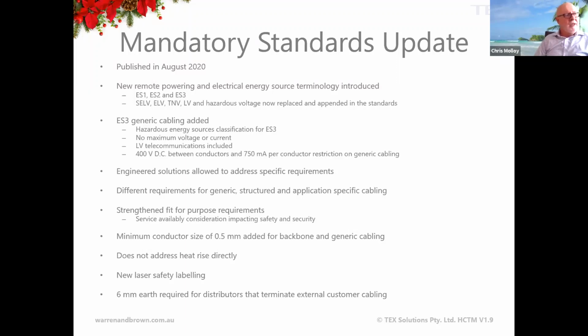There's a new naming convention now for remote powering and electrical source equipment, energy source equipment definitions. They come from a standard called AS/NZS 62368.1, and they have been applied. So we now have ES1, ES2, and ES3, replacing what we used to call SELV, ELV, TNV, and low voltage telecommunications and hazardous cabling. Those have been appended to the standards, and there is a changeover period for the next 18 months of swinging that terminology across. So if you haven't seen these standards, I can't implore you enough to get hold of them and get your head around how ES1, ES2, and ES3 apply.